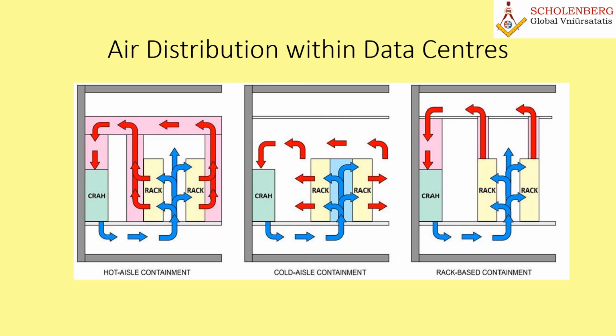if you see here, the underfloor delivery to cold aisles is provided and balanced using the range of airflow tiles available from 25% open to 63% open, and the fan boosted, which we already know happens below the floor. Then it comes out from the floor and gets distributed, and again as per the law of convection, it gets heated, and as it gets heated, the air density becomes lower, and the air passes above and again goes back to the unit. So this is how the underfloor delivery happens.